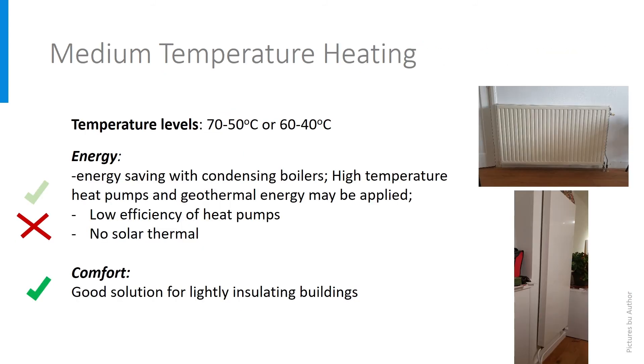Of course, between high and low temperature systems, everything in between is possible. In general, medium temperature is suitable in thermally renovated dwellings that do not achieve new-build insulation levels and in buildings with a little bit of insulation. It enables the use of condensing boilers, which have a higher efficiency, but still consumes fossil fuels. It also allows for the use of ground source heat pumps and medium temperature geothermal sources. However, the efficiency of heat pumps will not be very high and solar thermal cannot be applied. From the comfort point of view, it is an interesting solution in buildings that cannot be insulated easily.